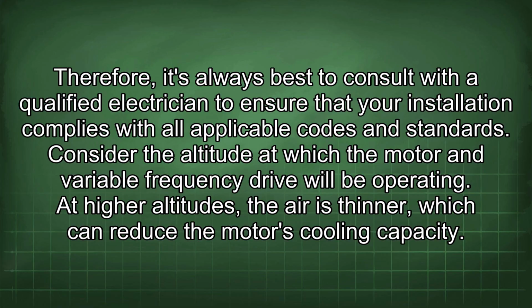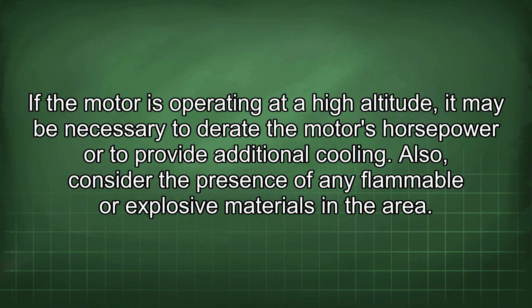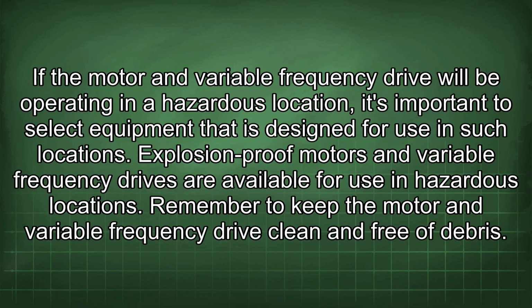At higher altitudes, the air is thinner, which can reduce the motor's cooling capacity. If the motor is operating at a high altitude, it may be necessary to derate the motor's horsepower or to provide additional cooling. Also, consider the presence of any flammable or explosive materials in the area. If the motor and variable frequency drive will be operating in a hazardous location, it's important to select equipment that is designed for use in such locations.